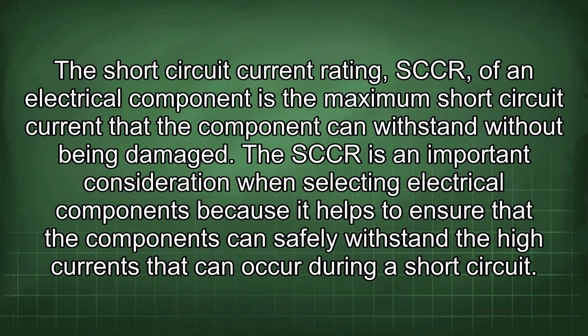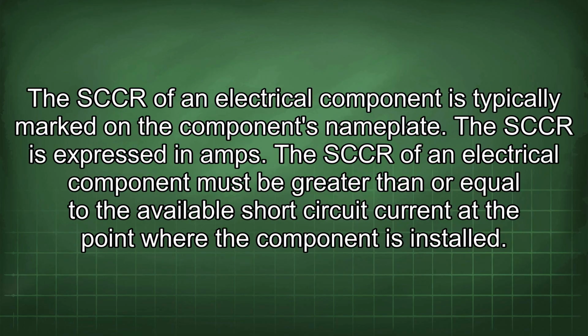The short circuit current rating (SCCR) of an electrical component is the maximum short circuit current that the component can withstand without being damaged. The SCCR is an important consideration when selecting electrical components because it helps to ensure that the components can safely withstand the high currents that can occur during a short circuit. The SCCR of an electrical component is typically marked on the component's nameplate. The SCCR is expressed in amps. The SCCR of an electrical component must be greater than or equal to the available short circuit current at the point where the component is installed.